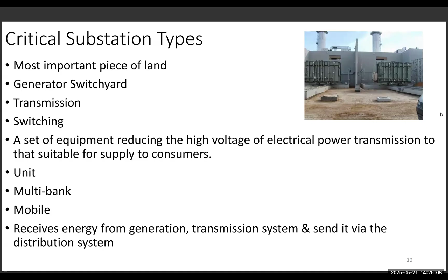Okay, now that we know what the different substations are, at least the name, the next thing is to focus on what do they do. Number one is transformation. Again, the example of going from Canada to New York City: if you didn't have the step up transformer to go from, let's say, 11 kV to 345, you're not going to have such a long line. And then at the other end, you go, let's say, from 345 back to 11 kV. So you have transformers at the substation to allow for the voltage transformation. That's the most important use case.